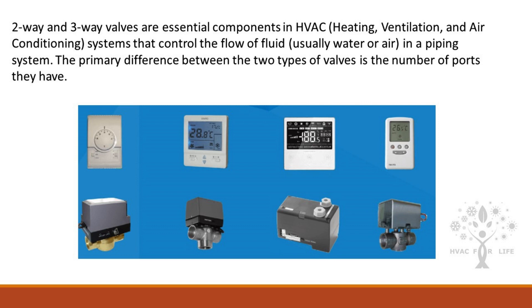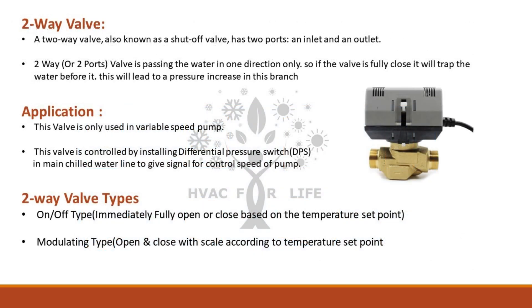The primary difference between the two types of valves is the number of ports they have. A two-way valve, also known as a shut-off valve, has two ports: an inlet and an outlet. A two-way valve passes water in one direction only, so if the valve is fully closed it will trap the water before it, leading to a pressure increase in that branch.